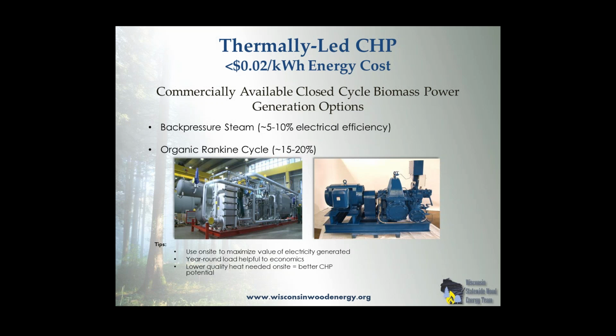I have to go back and count again, but I think it's in that range. I think there may be 7 of them that have been installed, and owners are generally very pleased with the system. The other option is an organic Rankine cycle system. An ORC is actually a little more electrically efficient. Overall thermal efficiency isn't any different. The challenge with organic Rankine systems is the investment is typically higher, and the quality of heat coming out of the system is also lower than it would normally be out of a back pressure steam system.